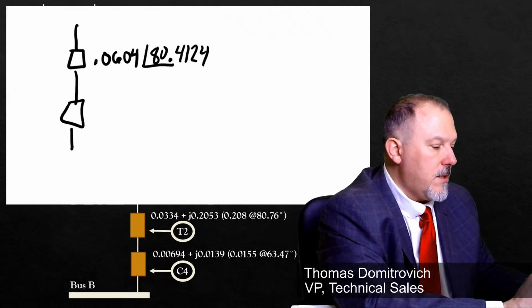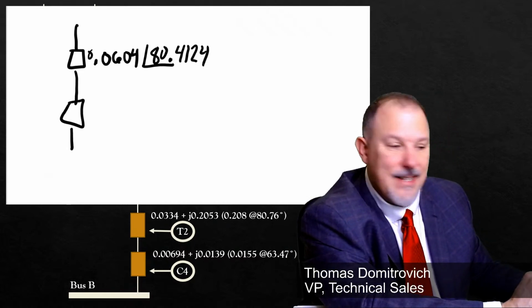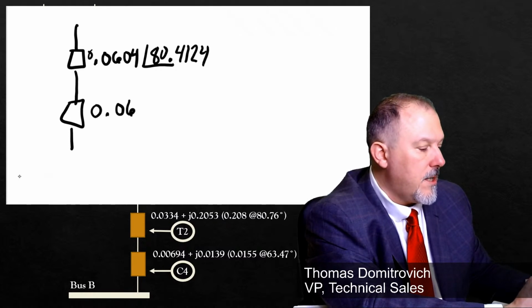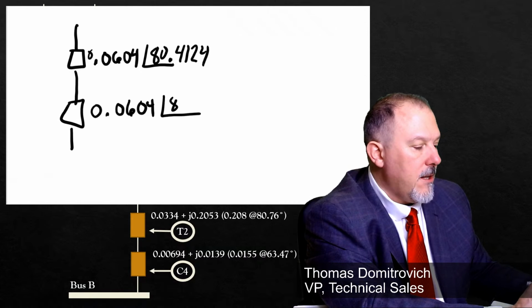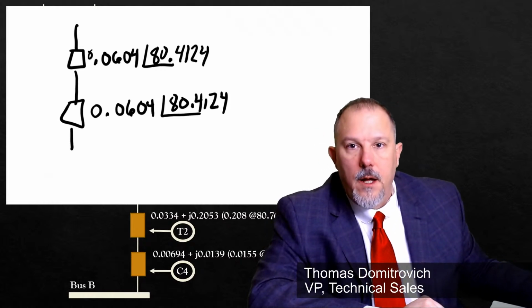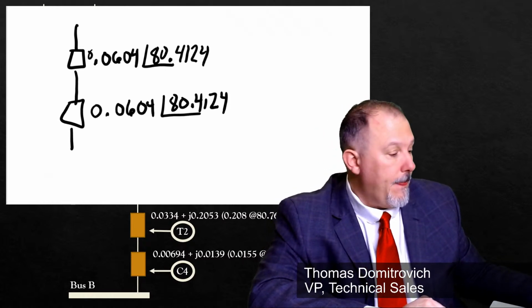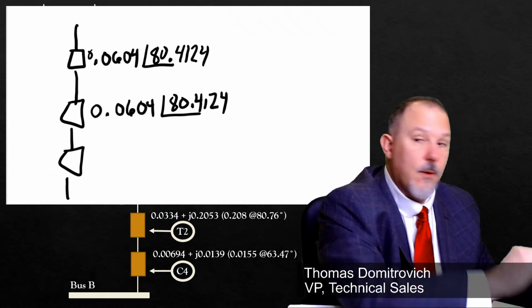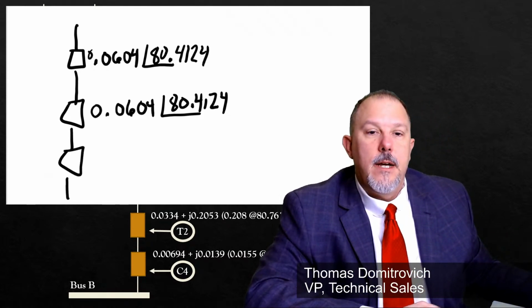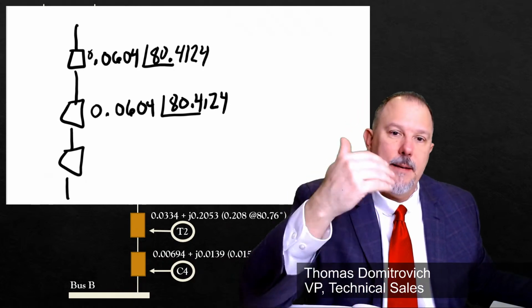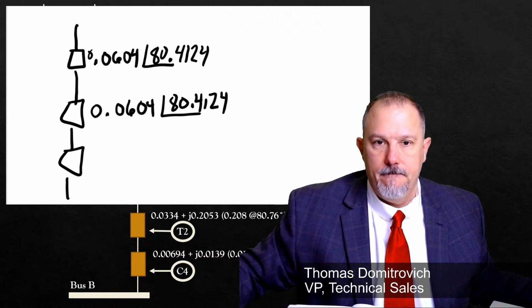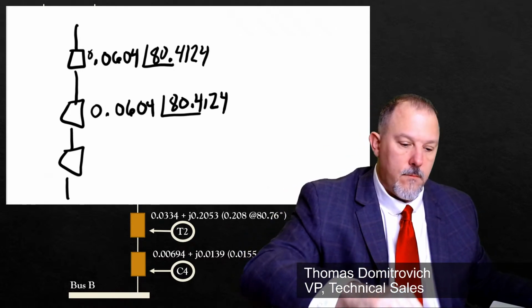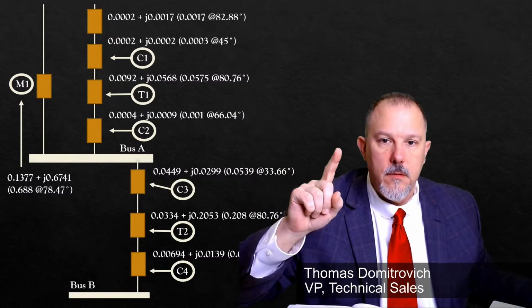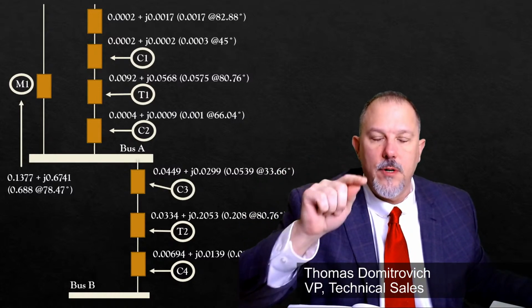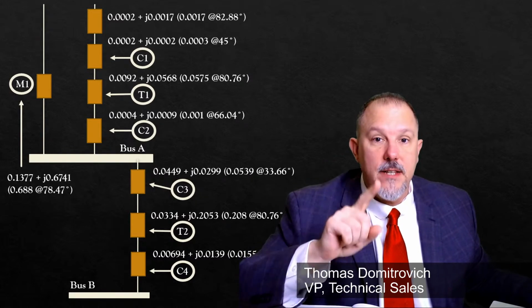That's the positive sequence. The negative sequence is exactly the same, 0.0604 at an angle of 80.4124. Make sense? Capiche? All right. Now I've got to do my zero sequence. Zero sequence currents or zero sequence impedance. Remember, I take only the transformer, which is 0.0575 at an angle of 80.76, and then the conductor, but I've got to modify my conductor.